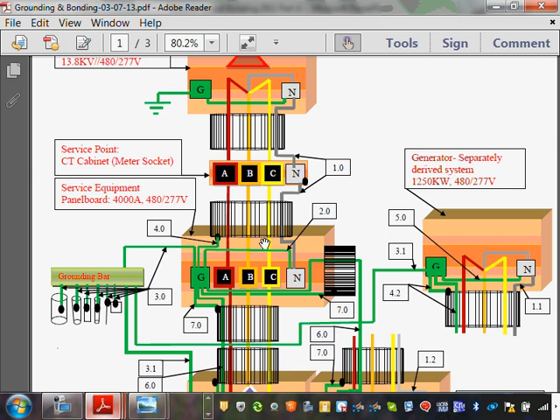So you come to the ground bar right here, and you take so-called number 3.0. I call it 3.0 for no reason other than I just want to label it. This conductor here is called grounding electrode conductor. It goes typically, doesn't have to be this way, but on bigger system, they have a ground bar sitting in the electrical room. And they grab that grounding electrode conductor, you tie it to that ground bar with irreversible means. And then from that ground bar, the reason why they put it outside so you can have access to it, measure, torque, do whatever you do, instead of getting inside the switch gear. Remember, you get into inside the switch gear, you got yourself with NFPA 70E and PPE and all this, that you have to put to go torque your grounding. So if you move it out, you have access to it.